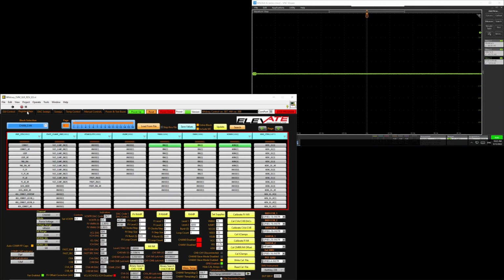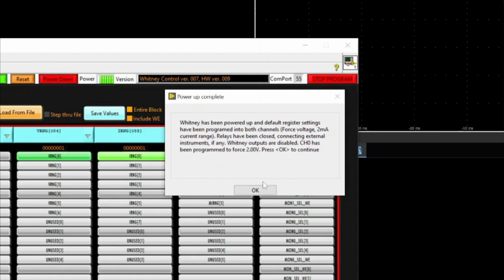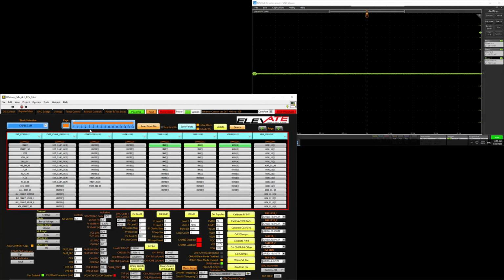Next, we will navigate back to the Registers Map tab. Upon powering up the device, Elevate has programmed a startup sequence that will set up but not connect the channel. This sequence programs the device to the default setups of force voltage mode, 2 mA range, and default compensation. All relays are closed, outputs to the Whitney are disabled, and the internal FV was set to 2 volts for channel 0. This tutorial will not cover the calibration, but assumes the device is calibrated. For more information on calibration, please review the datasheet and calibration guides.